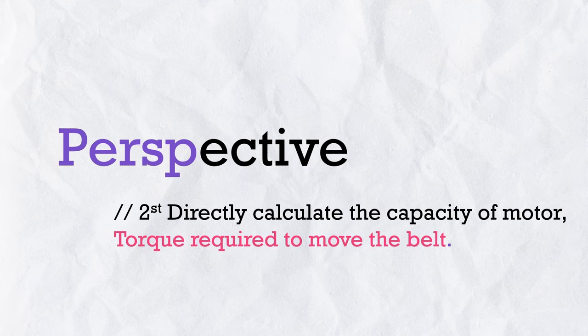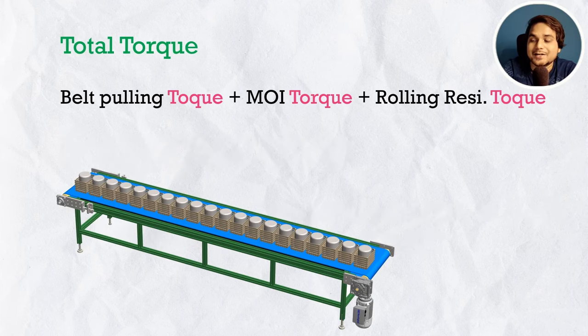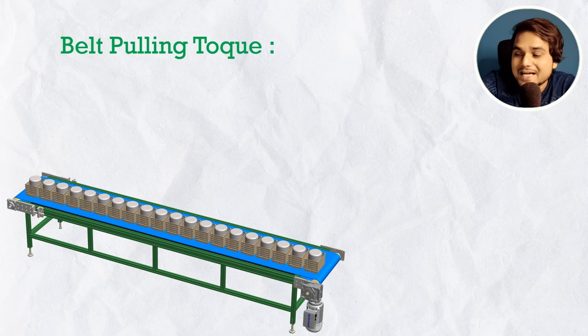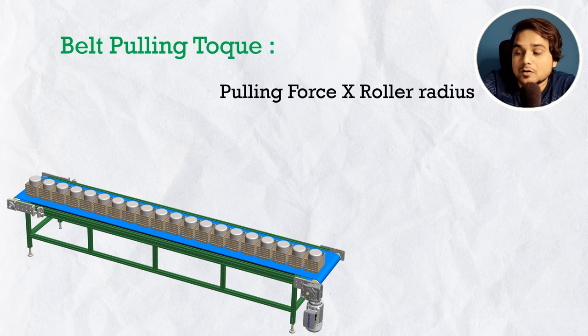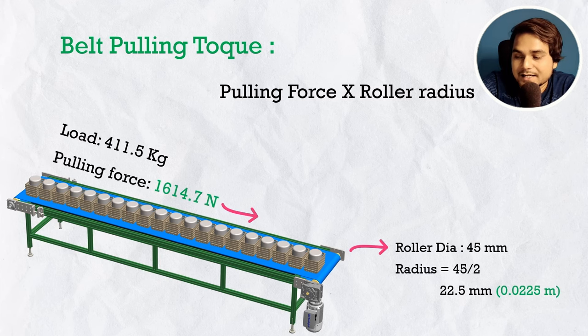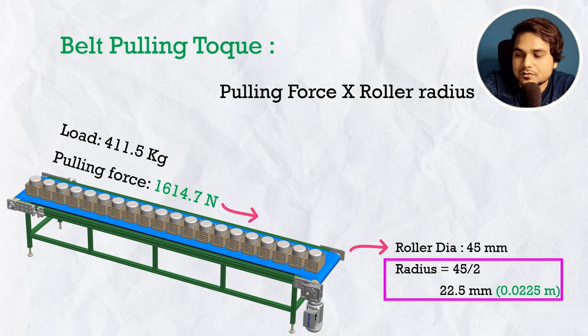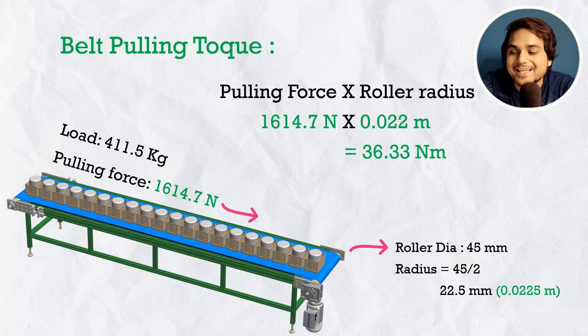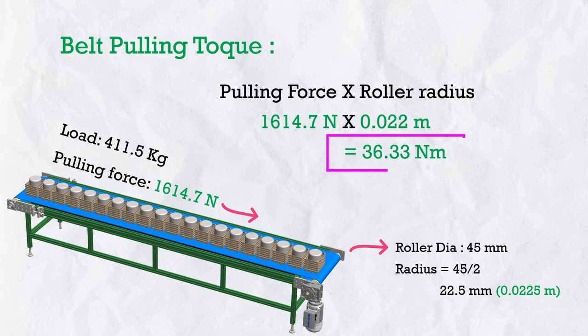So let's use the second perspective and directly calculate the required torque. Total required torque = belt pulling torque + moment of inertia torque + a safety factor for belt rolling resistance. First, belt pulling (load) torque: torque = pulling force × driving roller radius = 1614.7 × 0.0225 = 36.3 N·m. Interestingly, this matches the result from the first perspective — as it should.